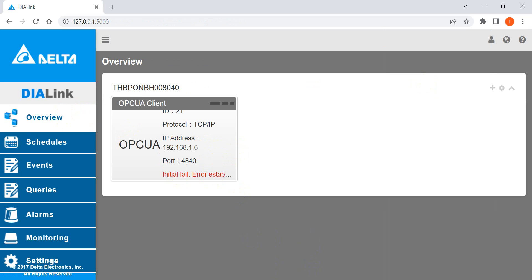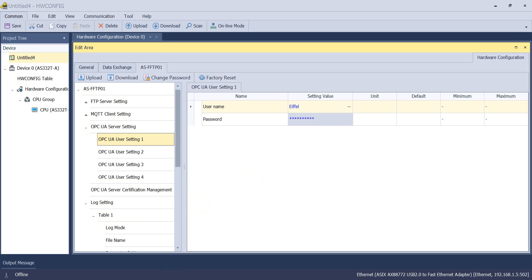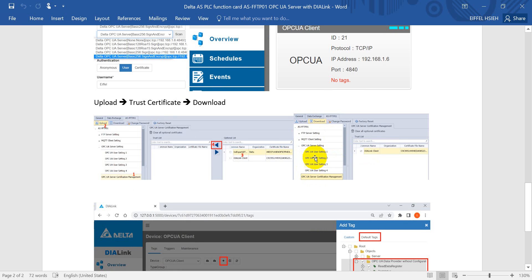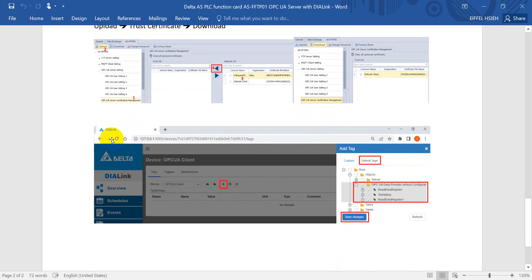To resolve the certificate trust issue, go back to the hardware config. Click OPC UA Server Certification Management, then click Upload. Once uploaded, you will see the certificate appear in the optional list — add it to the trust list. After adding it to the trust list, download the certificate to the PLC again. After that, try DIALink again and the connection will be successfully established.